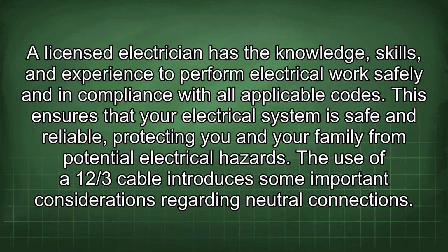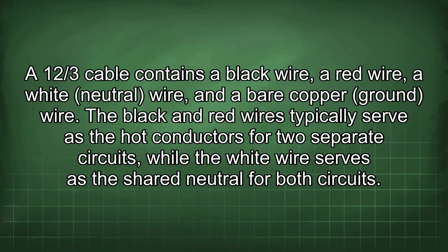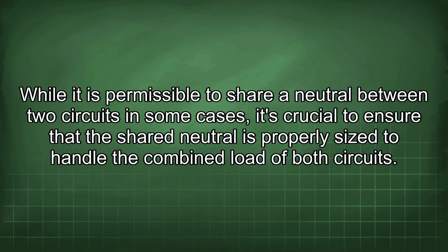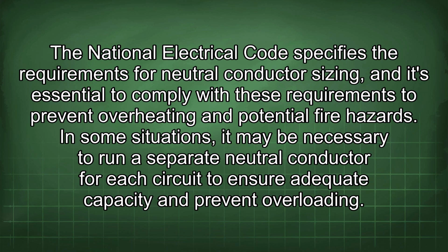The use of a 12/3 cable introduces some important considerations regarding neutral connections. A 12/3 cable contains a black wire, a red wire, a white neutral wire, and a bare copper ground wire. The black and red wires typically serve as the hot conductors for two separate circuits, while the white wire serves as the shared neutral for both circuits. While it is permissible to share neutral between two circuits in some cases, it's crucial to ensure that the shared neutral is properly sized to handle the combined load of both circuits. The National Electrical Code specifies the requirements for neutral conductor sizing, and it's essential to comply with these requirements to prevent overheating and potential fire hazards. In some situations, it may be necessary to run a separate neutral conductor for each circuit to ensure adequate capacity and prevent overloading.